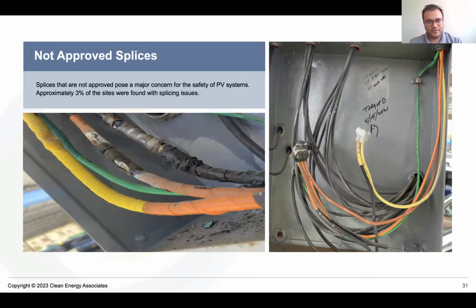This is a picture of splices we found in a pull box, at one of the big box stores we inspected. On the right, you see cables connected using splices, with tape on them. When we asked the technician supporting our inspection to take off and unwrap the tapes, we found there were actually more splices than were visible, and there were burnt marks on these splices.